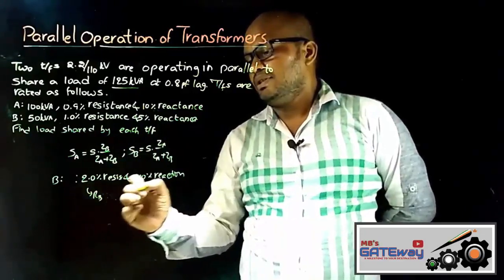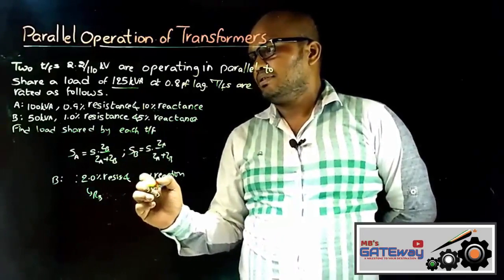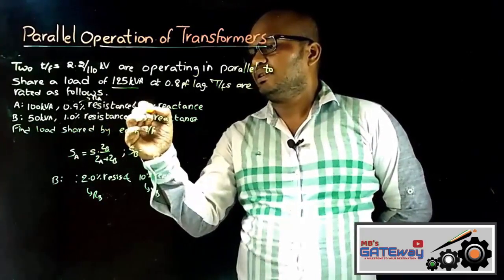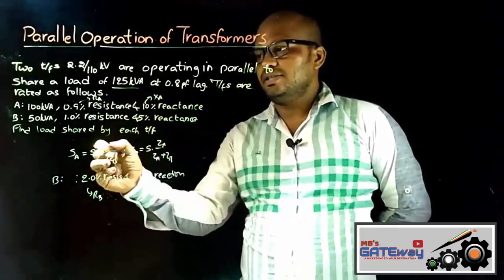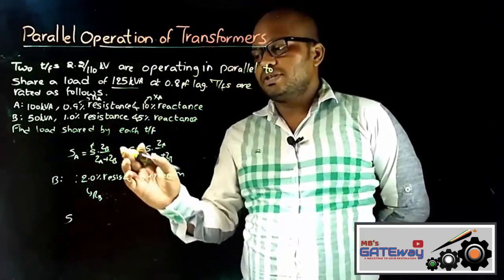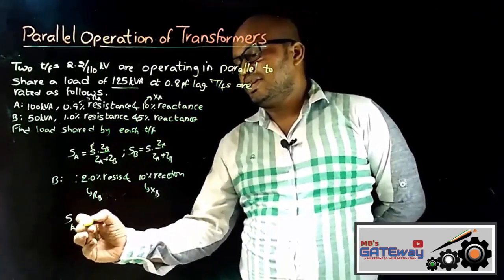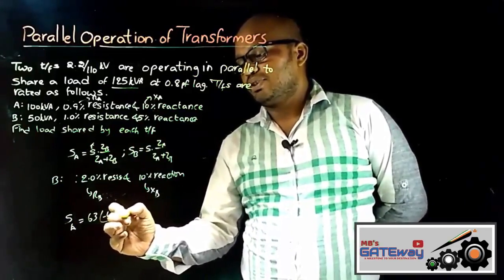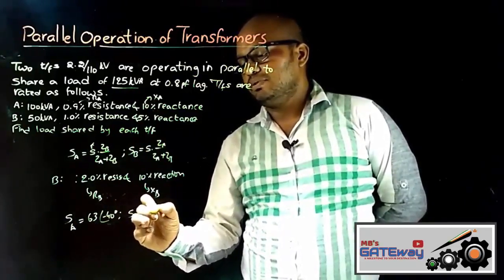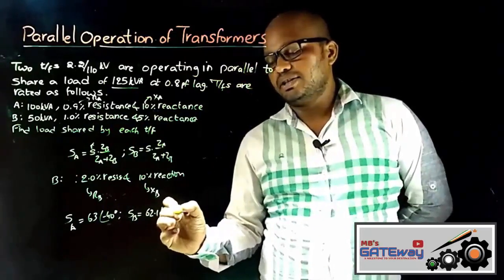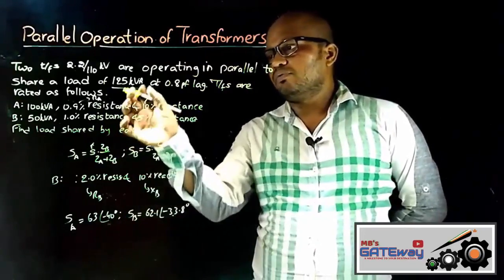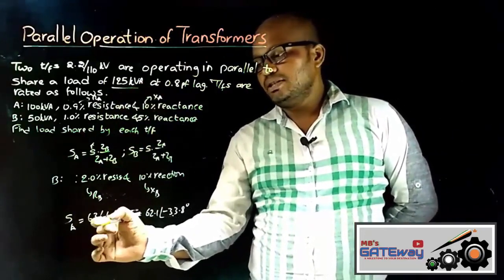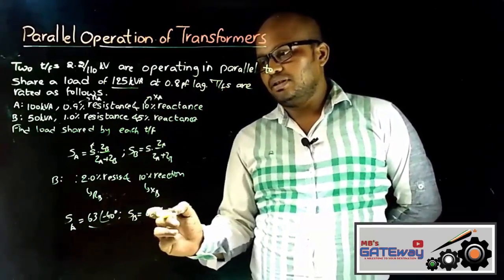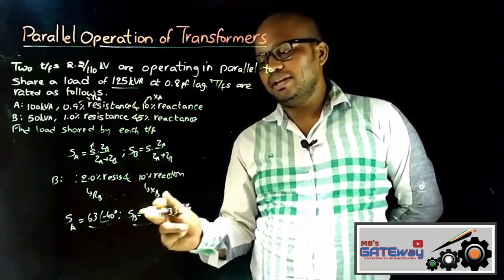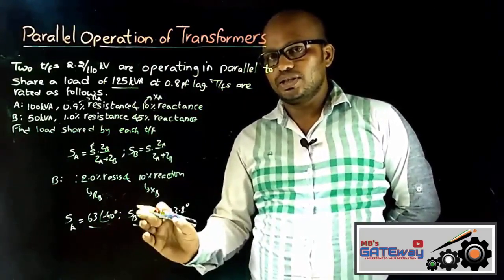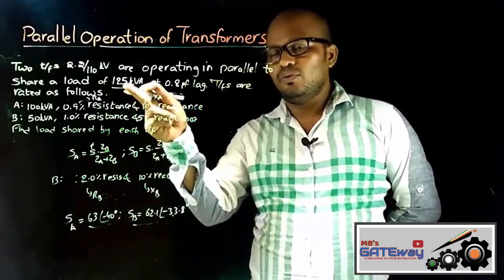This is RB and this is XB, and this is RA and this is XA, and S is 125 kVA. And now by substituting all these values and solving, we will get SA is equal to 63 at an angle minus 40 degrees, and SB is equal to 62.1 at an angle minus 33.8 degrees. So of 125 kVA, transformer A supplied this power, and transformer B supplied this amount of power. Means these are the loads shared by transformer A and transformer B of 125 kVA.